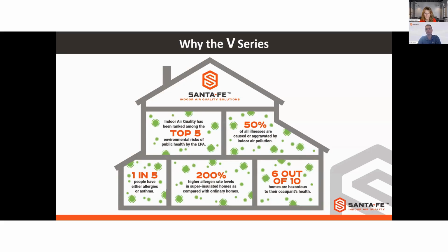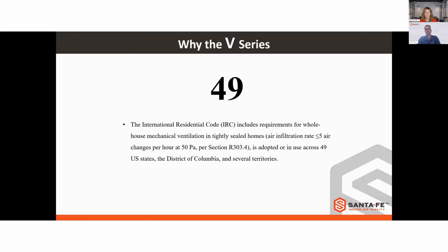So if you're in the industry or have been in the industry for a while, you have known that there has been a lot of focus on indoor air quality. ASHRAE 62 is addressing this. And so we really wanted to invest the ventilation feature of our new units into being able to address these issues. So 49, what's 49? The International Residential Code, the IRC, includes requirements for whole house mechanical ventilation in homes that are less than 5 ACH, air changes per hour. And this is adopted across 49 states in the US, the District of Columbia, and several other territories.